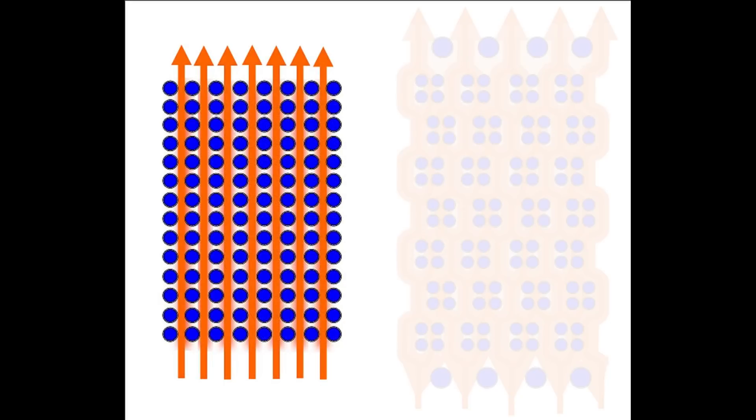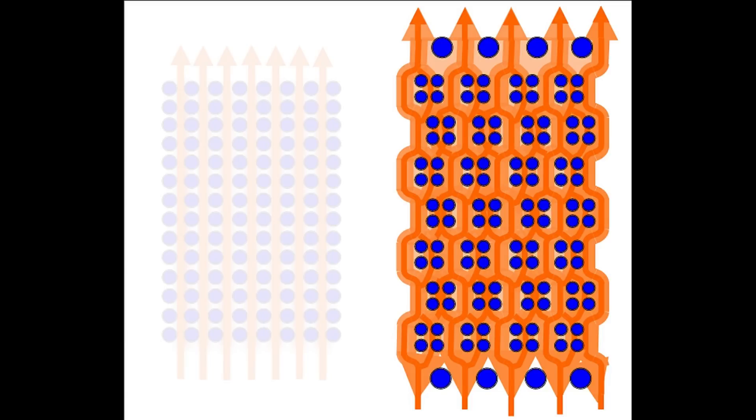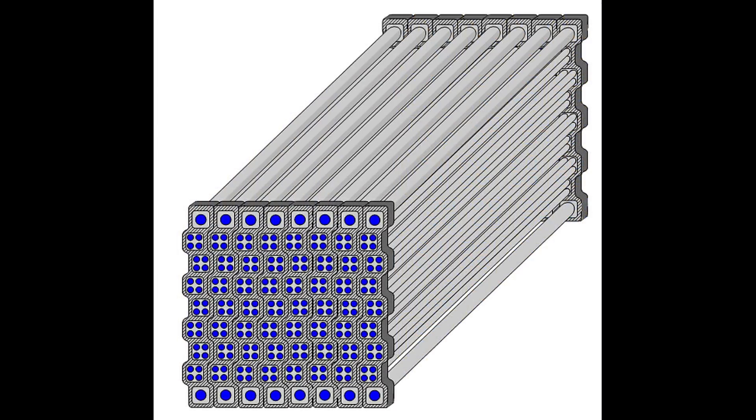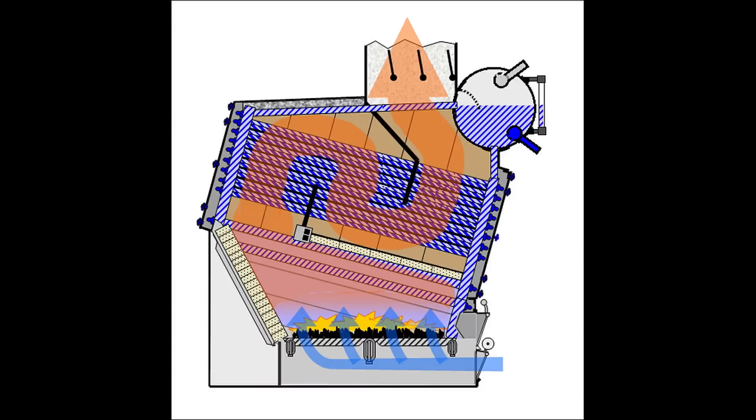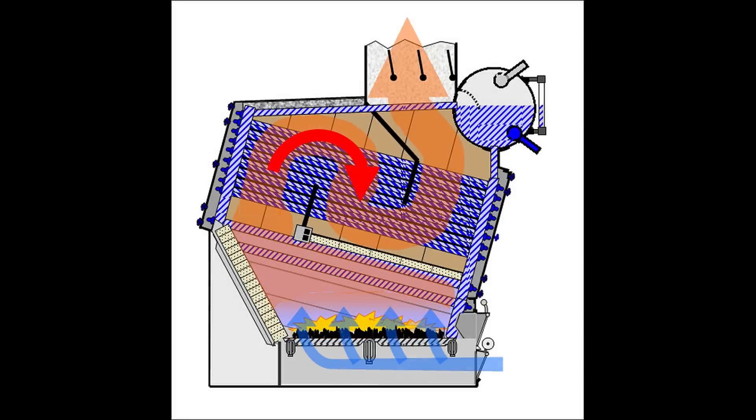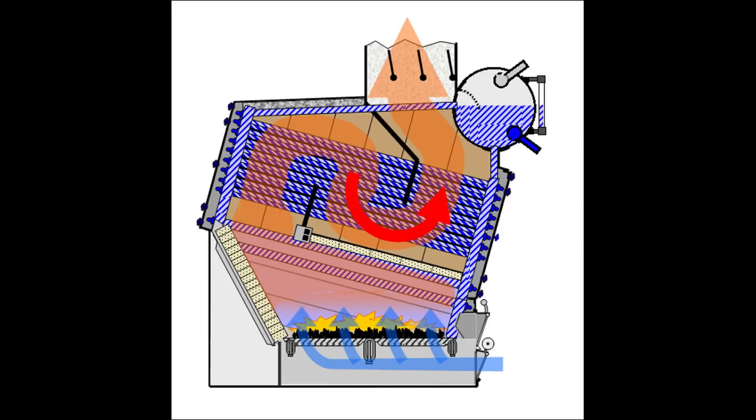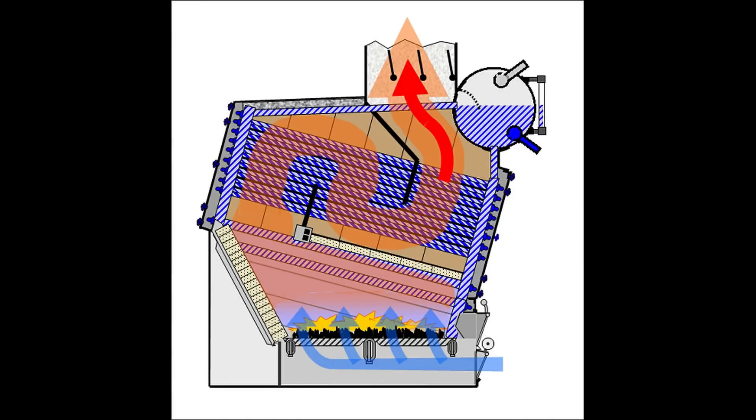The speed and manner that hot gases moved across the tubes was also very important. Burning gas flowed very quickly, meaning it could move between the tubes and leave through the uptake without passing much of its heat to the tubes. To slow things down and improve circulation around the tubes, they were bundled into groups of four and placed in staggered rows rather than being neatly lined up. With that, gases slowed as they curved back and forth around the bundles and were forced to more completely surround the tubes. The result was better heat transfer and more uniform heating of tube surfaces. Gases were also carefully routed as they moved in the firebox, around the tubes, and out the uptake. It started in the firebox, whose roof was sloped, becoming taller toward the rear. This encouraged complete mixture with air for maximum combustion and directed the superheated gases into the tube bundles. It was there that a series of baffles routed them up across the tubes, back down to cross them again, and then up again one more time before being exhausted through the uptake. The three changes in direction slowed the gases down even more and provided three opportunities for them to give up their heat to the tubes.